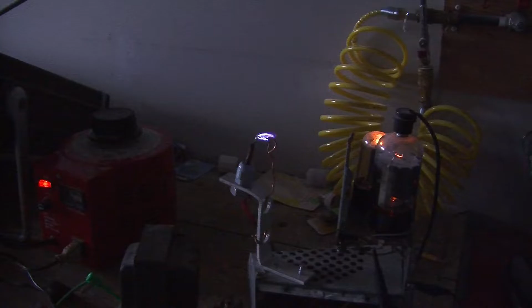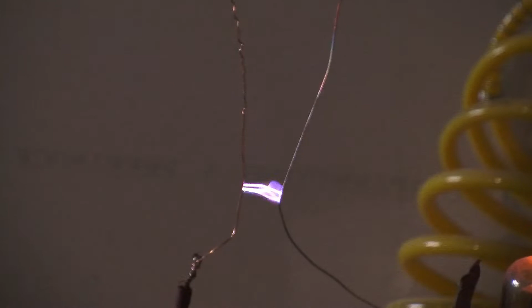Now, even with an isolation transformer, what can go wrong? Well, remember my video about the 20 kilovolt high voltage generator? If somehow that 20 kilovolts were to end up on the windings of the isolation transformer, it could easily puncture the insulation and turn the isolation transformer into not an isolation transformer and potentially allow currents to flow through the body. So the bottom line is, if you're dealing with very high voltages, an isolation transformer is not going to help you.